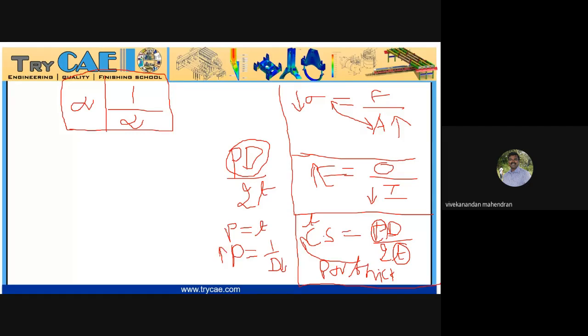Say I designed one double pipe heat exchanger at near about 200 bar. If my pressure is 200 bar, then my diameter has to be very less. The reason is it's inversely proportional, in the circumferential stress formula PD by 2T. Then I will discuss another most important thing I learned from experience.